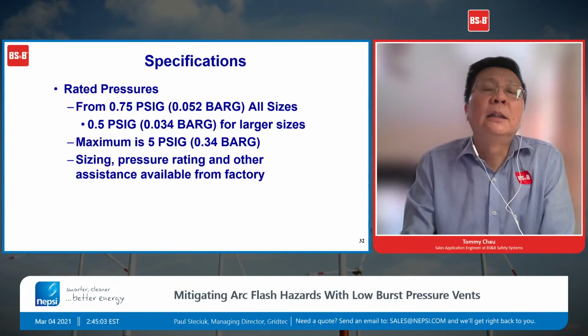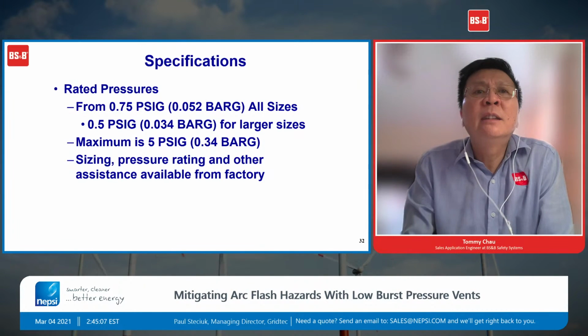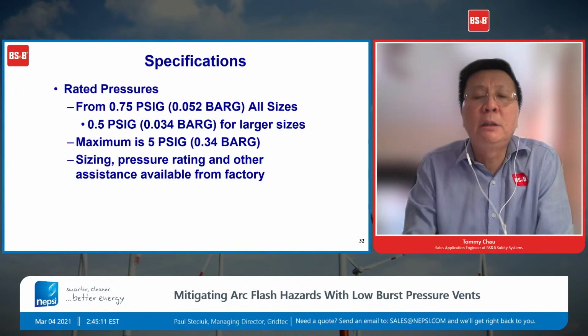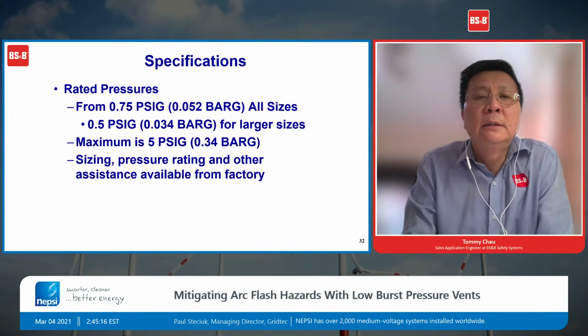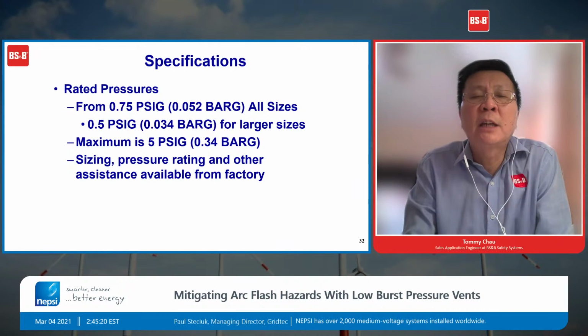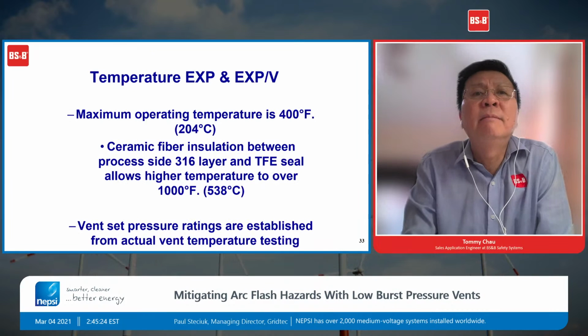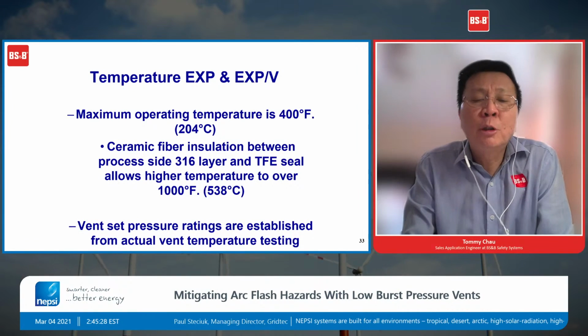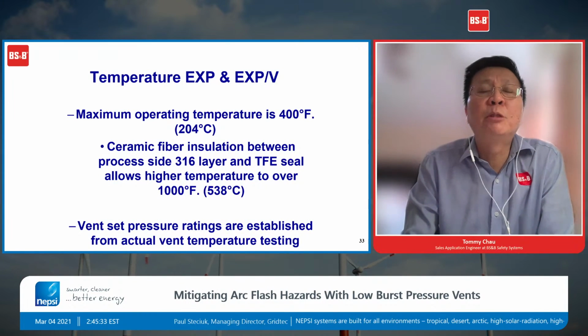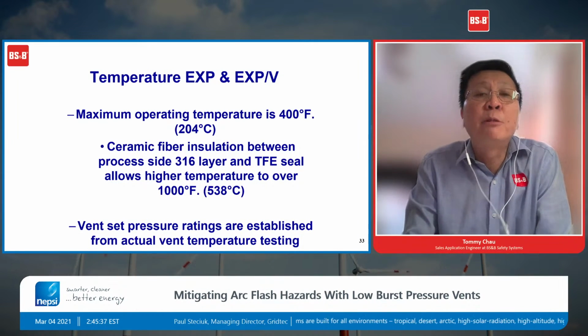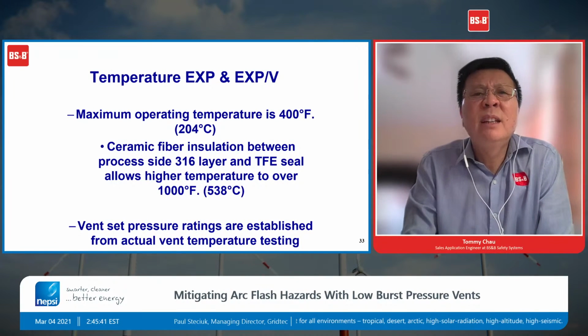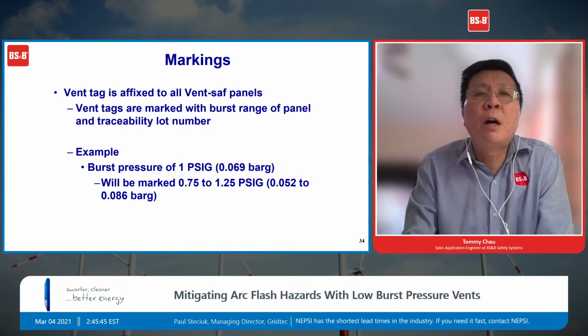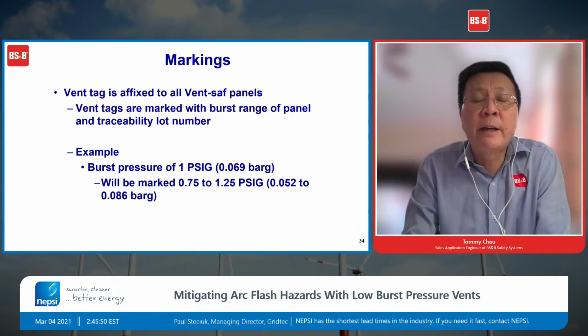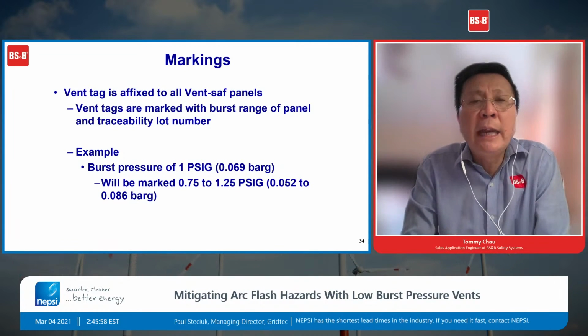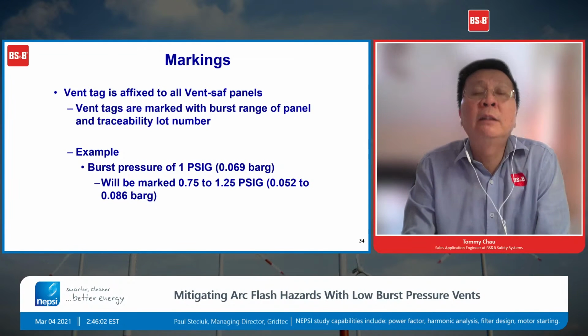Again, we get into burst pressure of explosion vents, half a psi on a lot of the bigger vents, and typically we don't get anything higher than 5 psi on the higher end of the maximum pressure. So half a psi, 0.75 psi, up to 5 psi. We also have operating temperature. We typically design our explosion vent to withstand the operating temperature inside the equipment. On explosion vent marking, as Paul mentioned earlier, we provide a name tag on all of our explosion vents. It gives you the minimum and maximum burst pressure, the opening area, and the temperature. So that's all well identified on the name tag.